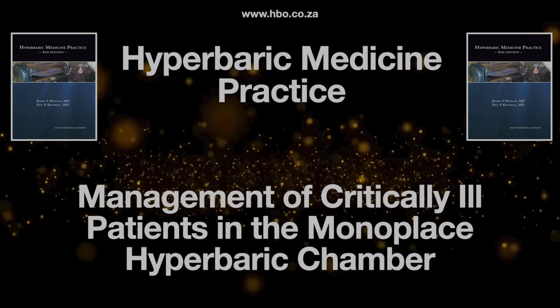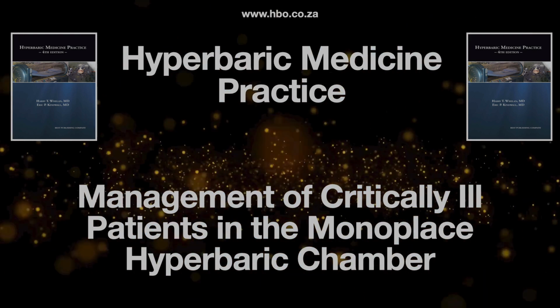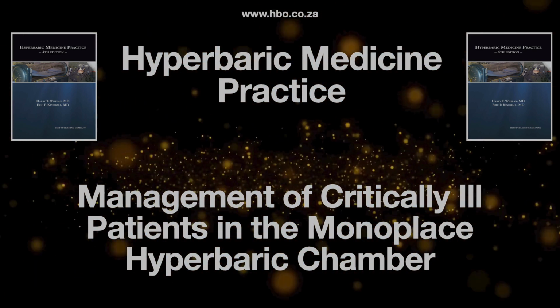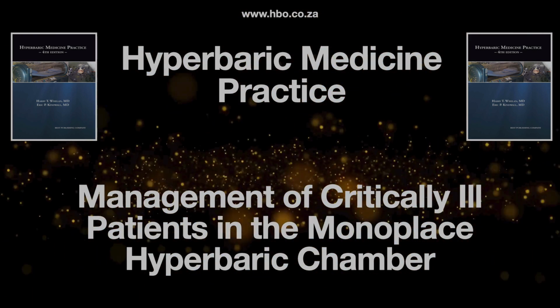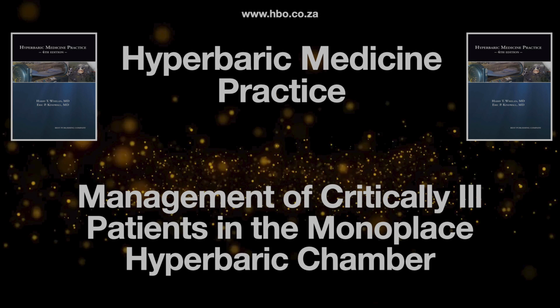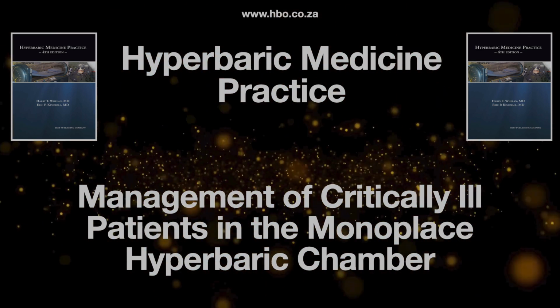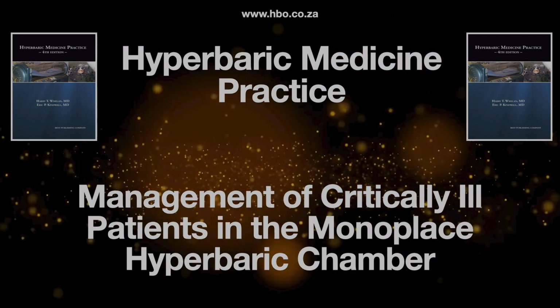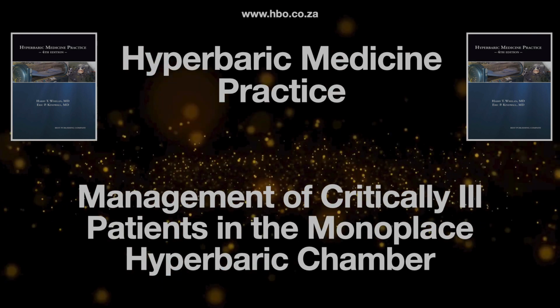Several key things. You need electrical pass-throughs to connect monitors outside to the patient inside. Same for IV lines. Fluid and drug pass-throughs are essential for continuous infusions, and a gas pass-through for the ventilator hose. Beyond that, there are more specialized things, like systems for suctioning drains inside the chamber, ways to give short air breaks during ventilation, non-invasive BP monitors that work under pressure. Air break. Yeah, short periods breathing air instead of 100% oxygen to reduce toxicity risk.